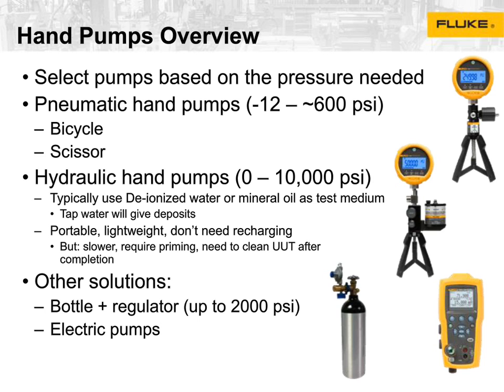So they've got some nice advantages, which I talk about here. You know, they're portable and lightweight, and you don't need to charge them the way you would with, say, a nitrogen bottle. But as we talked about, you do have to prime them. They are a little bit slower, and you're going to have to clean the unit after you finish pretty frequently, especially if you're applying it in a dry gas environment, say natural gas. Even if you use DI water, you really should clean the unit under test. Couple other solutions I've listed here.